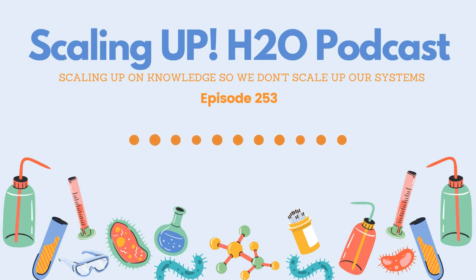In general, foamers are a good thing, especially in an unsaturated system like a cooling tower. It's important to get the antimicrobial into contact with the biofilm, and this can be a challenge in many systems, not just cooling towers. So this issue of access to the biofilm for the antimicrobial is really important to consider.